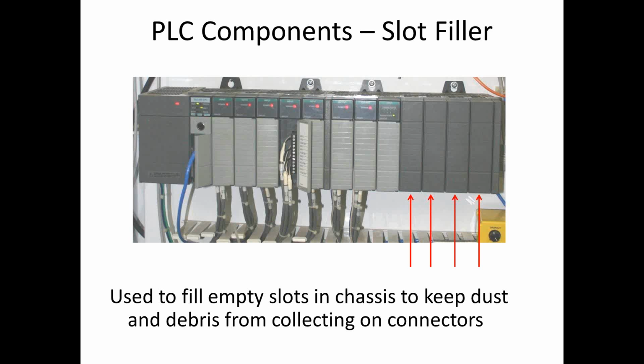There are slot fillers. We've seen those before, where you've got a spot for cards but you don't have the cards available, so you just put in these slot fillers, and they're used to fill empty slots in the chassis to keep dust and debris from collecting on the connections. I said the PLCs are robust, that they can operate in pretty harsh conditions. However, dust and heat are their two main enemies, and you want to try to combat that if you can. So using these slot fillers, you can help keep the connections clean.